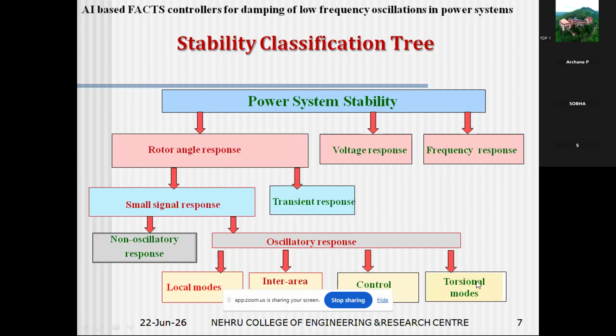The turbine, the shaft, etc. will be having modes of oscillations. That is a mechanical oscillation, and this is the control oscillation. Both these types of oscillations are actually something to be addressed by controlling the damping part of the system. In today's presentation, we will look into these two types of oscillations and how they can be addressed, by looking into the rotor angle response when it is subjected to a small disturbance and when it has an oscillatory response in these two modes.